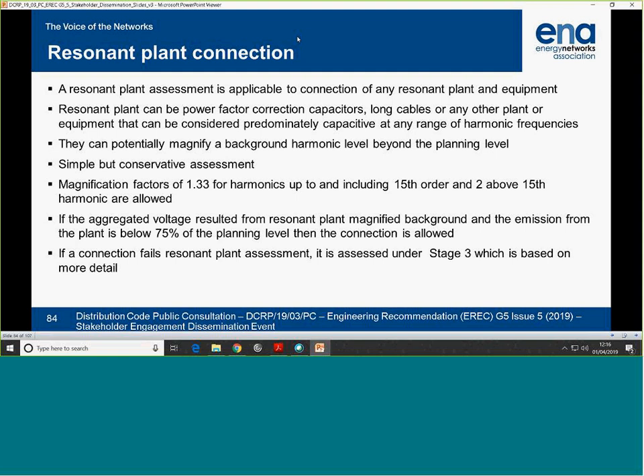The standard connection agreements say comply with G54. I'm just saying, if it's our cable or if it's your cable, does it make a difference? The timescales for quoting are set so that the G5 studies are not done before the quote goes out. So there doesn't seem to be an opportunity to do that up front. You accept it's going to take longer to quote.